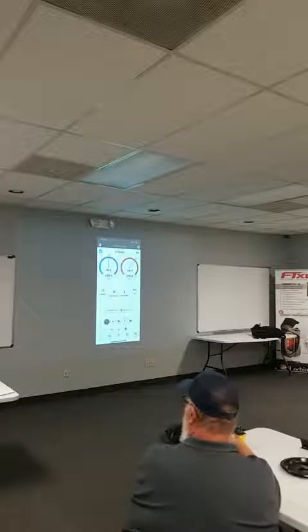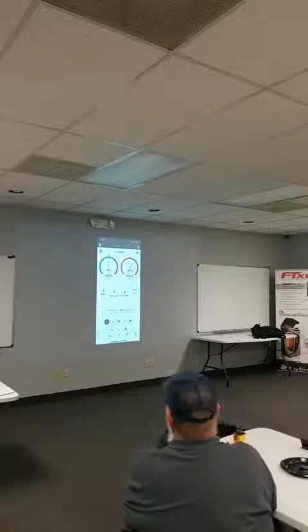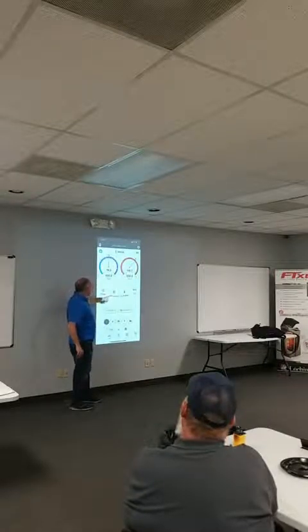So in other words, you can do 350, you can do 400, you can do 450. Any one of those airflows is correct, it just depends on the latent sensible split that you want on the machine, right? But what we did is we said, okay, we're getting a lot of people that aren't adjusting that, so we're going to put in the full range of airflow. So if you slow your airflow down to 350, it'll be closer to this end. If you go up to this end, it's going to be closer to 450. Right now, this is 379 per ton, so it's just below that.